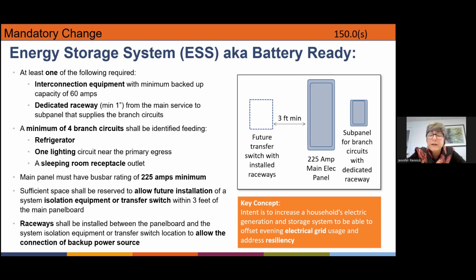And the panel size now would have a minimum bus bar rating of 225 amps, up from 200. There are other requirements on how you'd set up that sub panel for the branch circuits, including having a place for a future transfer switch with installed raceways. So this battery-ready part is going to impact some of the work electricians do on new construction residential projects.